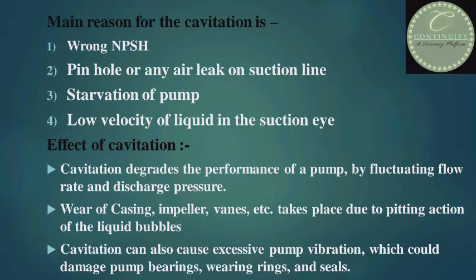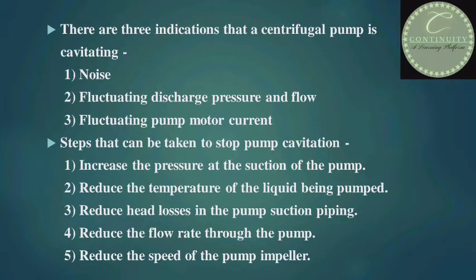Wear of casing and impeller vanes takes place due to the pitting action of the liquid bubbles. Cavitation can also cause excessive pump vibration, which could damage pump bearings, wearing rings, and seals. Indications that a centrifugal pump is cavitating include: noise, fluctuating discharge pressure and flow, and fluctuating pump motor current.